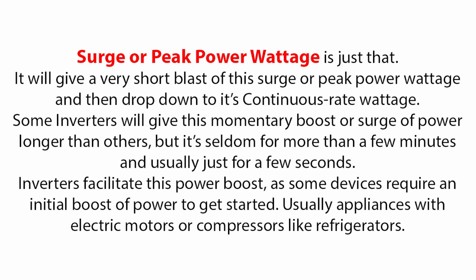Just to explain what surge wattage or the peak power wattage is, some appliances, particularly those with electric motors, need an initial boost of electric power in order to get started. That boost of electric tends to drop back down to its regular stated continuous power consumption as soon as the appliance gets running steadily. So, most inverters have a surge factor built into them to compensate for this initial guzzle of electric power that is required by some electrical devices to get started. That surge often being created by anything with an electric motor in it that just needs that extra boost of power, or an electrical kick in the pants to get it started.